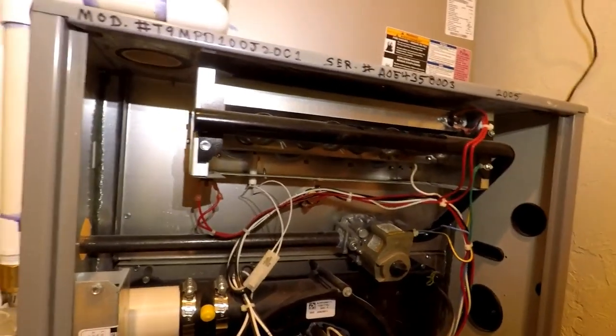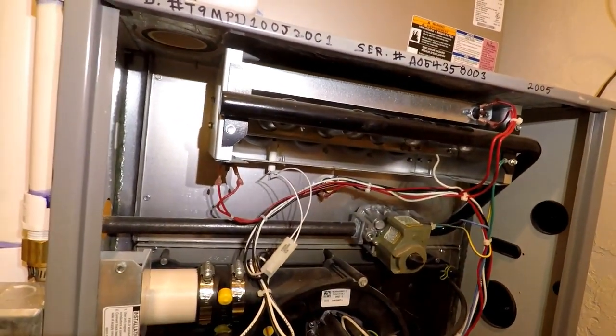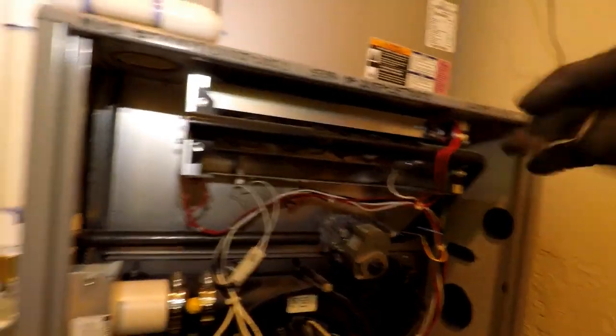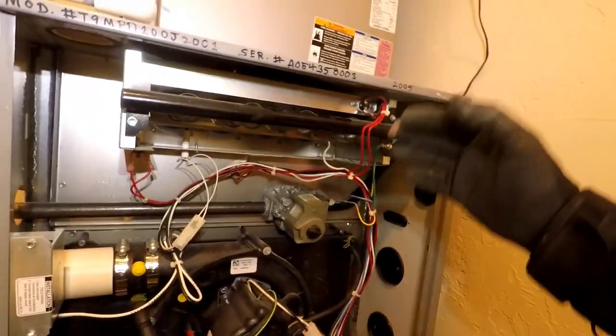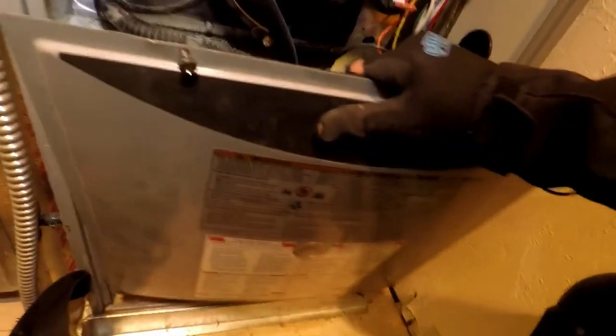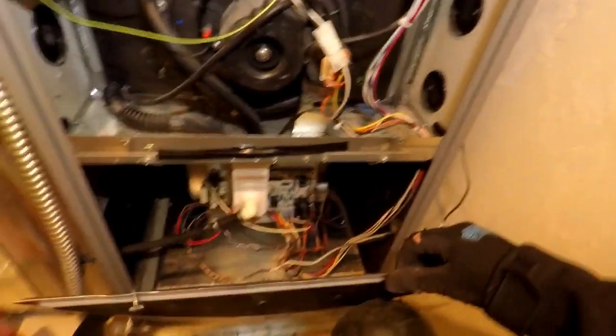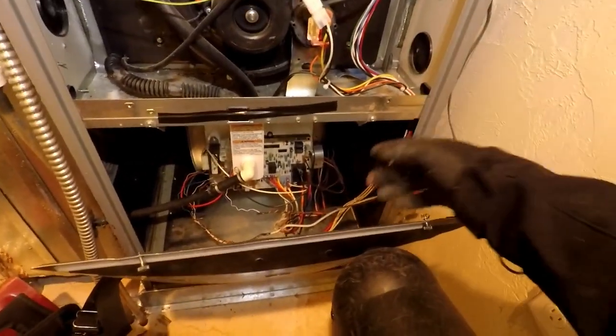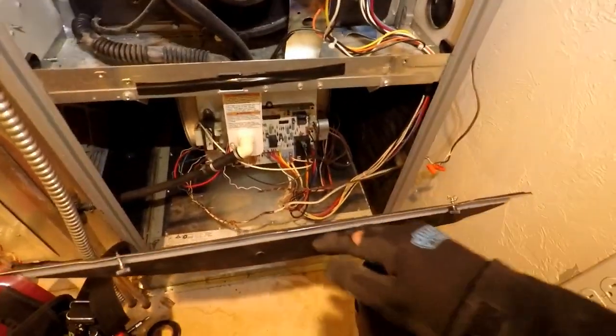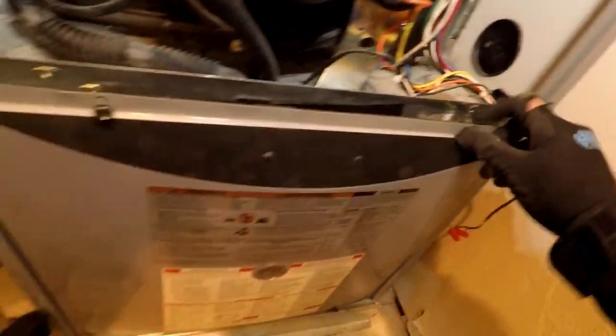The most common thing that I've seen with those is the heat exchanger starting to plug up. Usually the secondary, and then the flame can't get through it well, and then it rolls out the flame. So we're going to put this cover back on the bottom because we don't want the air, when the blower motor comes on, pulling that flame back here because of air pressure, so we'll keep that on there.